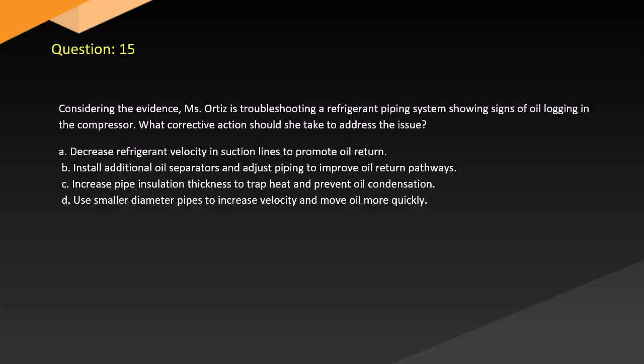Question 15. Considering the evidence, Ms. Ortiz is troubleshooting a refrigerant piping system showing signs of oil logging in the compressor. What corrective action should she take to address the issue? A. Decrease refrigerant velocity in suction lines to promote oil return. B. Install additional oil separators and adjust piping to improve oil return pathways. C. Increase pipe insulation thickness to trap heat and prevent oil condensation. D. Use smaller diameter pipes to increase velocity and move oil more quickly.